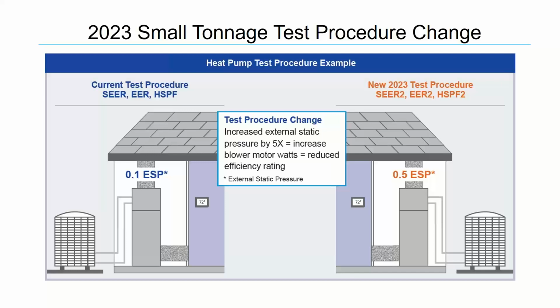All of those things used to be tested at 0.1 inches of external static pressure, which is very close to nothing. It's very little resistance. It's basically like, hey, if I put 5 feet of duct on this furnace, how restrictive would it be, right? Let's go ahead and test the unit that way. The new testing standard that began this year requires us to test all the equipment at 0.5 inches of external static pressure, which means the indoor fan has to run at a higher wattage in order to move the amount of air we need to move for the AC. So that does, in fact, change our rating.